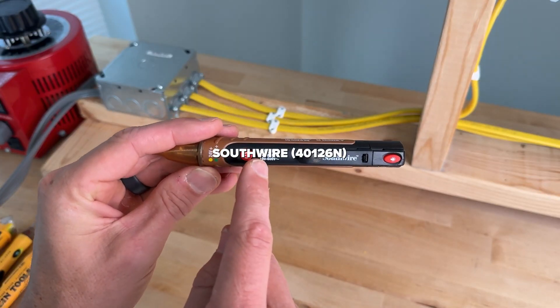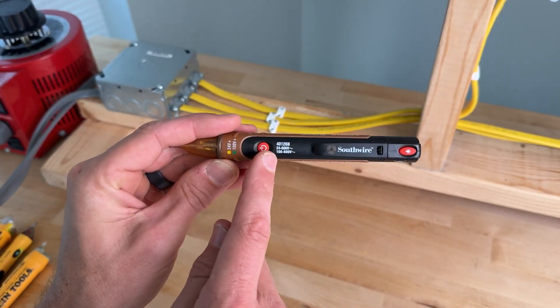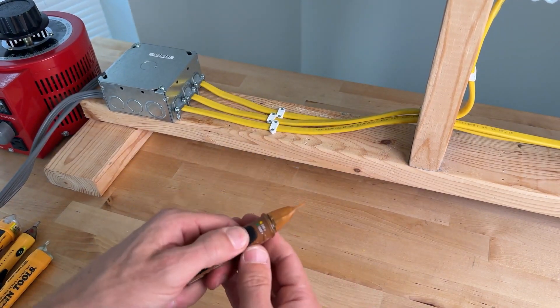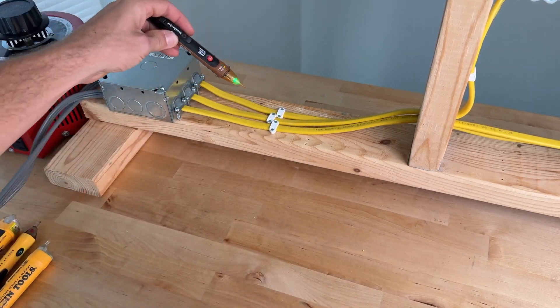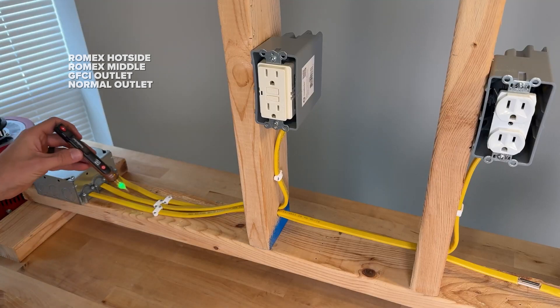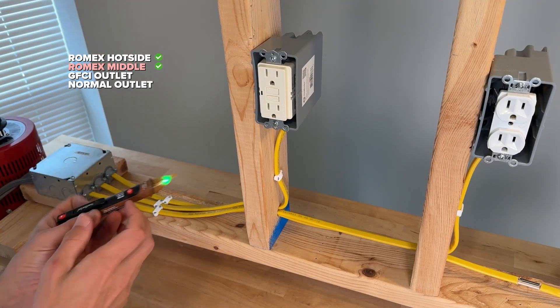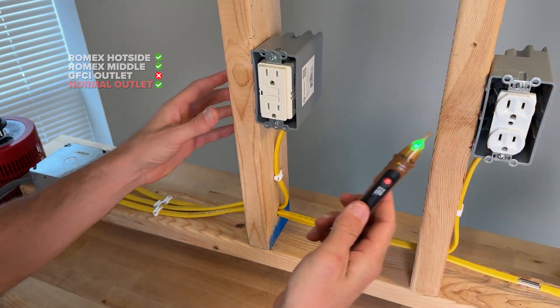The Southwire 40126N has two different voltage ranges: 24 to 600 volts and 100 to 600 volts. It also has an integrated light at the end. With a momentary press you get a green LED with audible alarm. Testing: first test good, second test good, GFCI — no — and duplex good. So the Southwire fails the GFCI test.